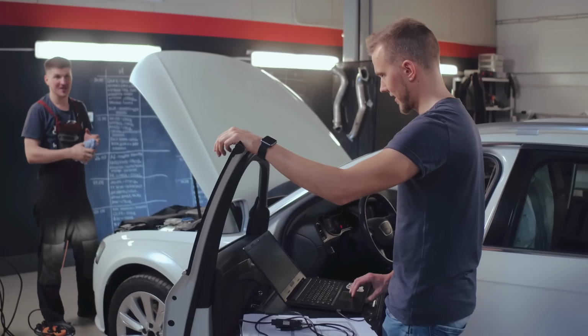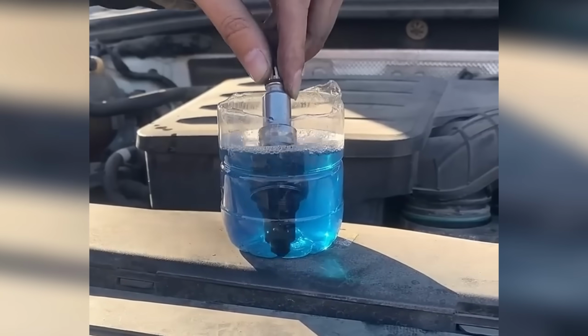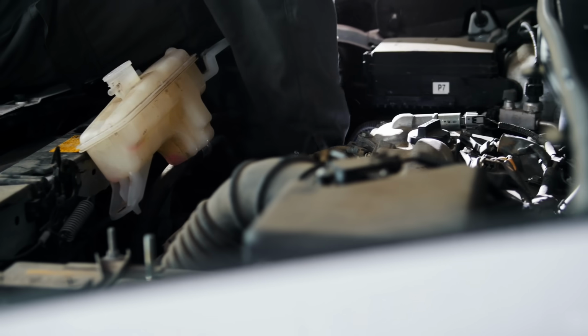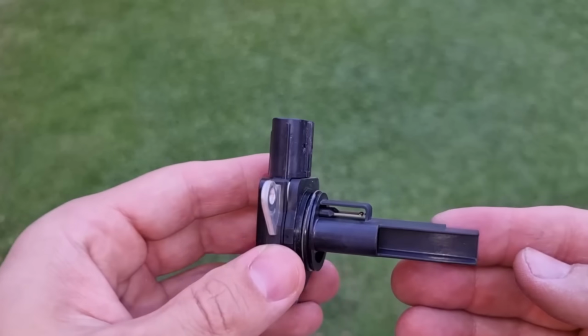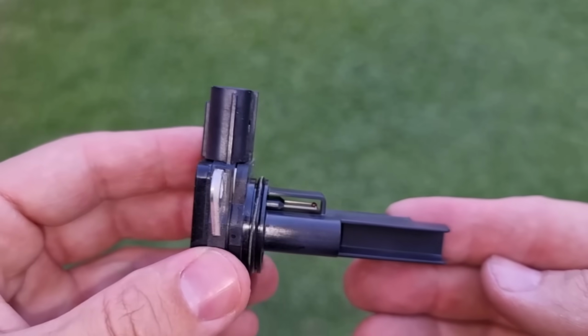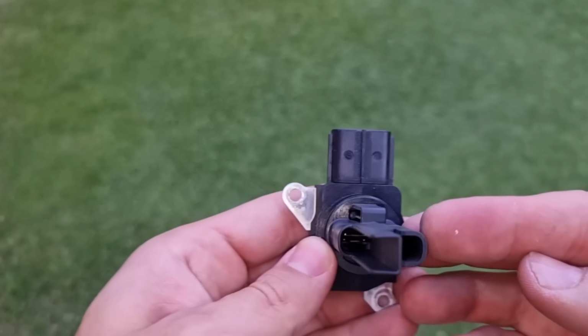The protocol is simple. Submerge the sensor tip and gently agitate every 5 minutes. Extending the soak to 45 minutes showed diminishing returns. 30 minutes is the sweet spot. Once your sensor is perfectly clean, the drying method becomes your next critical decision point.